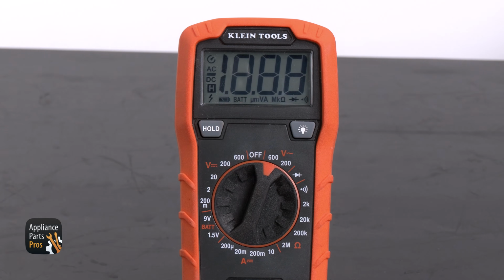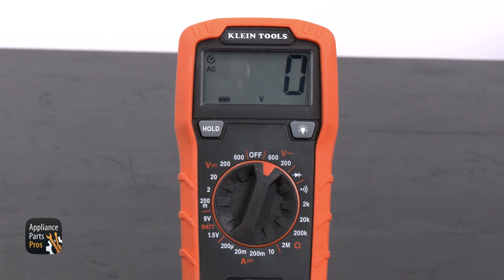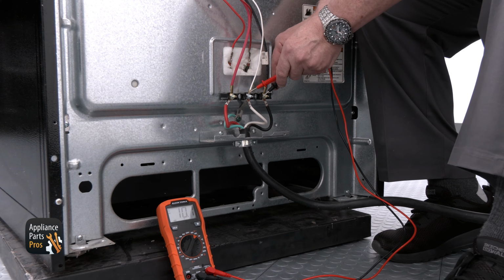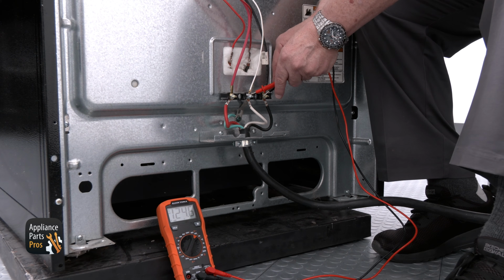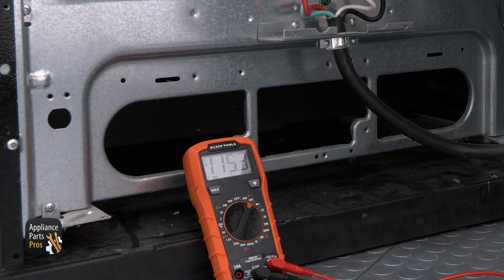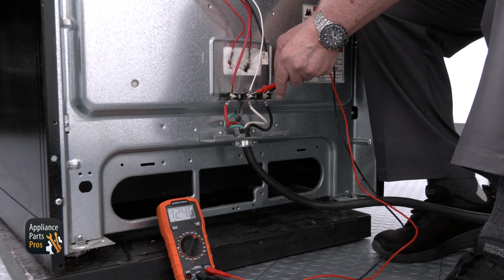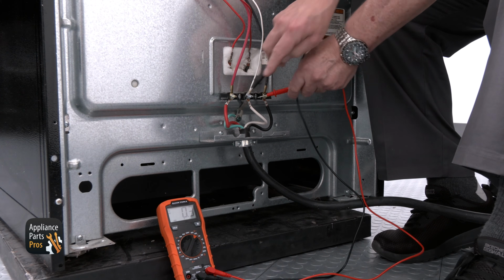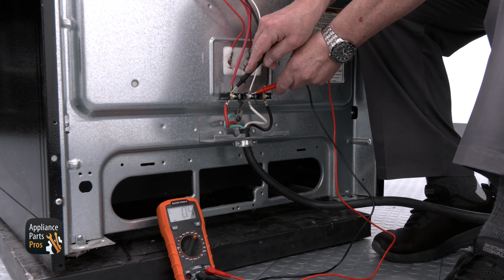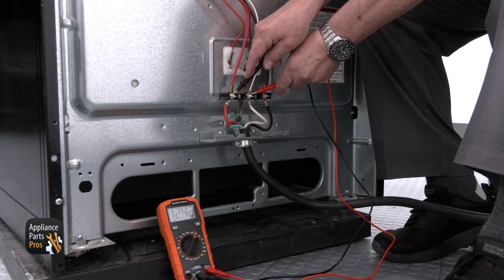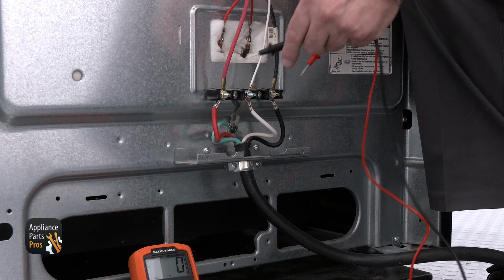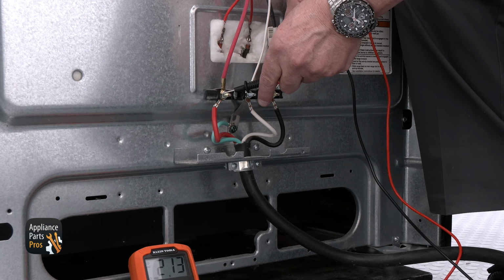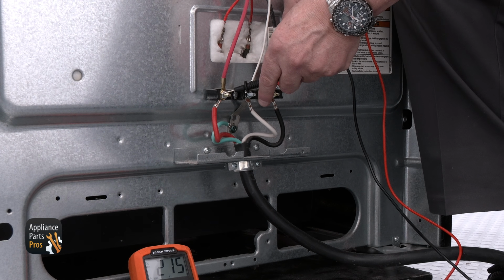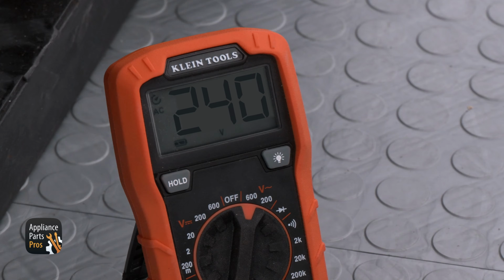Use your multimeter set to volts AC and put one probe on the white terminal and the other probe on the black. You should get a reading of 120 volts AC. Then move the probe to the red terminal and keep the other probe on the white wire. You should see 120 volts AC. Finally, move one probe to the red terminal and the other probe to the black, and you should see 240 volts AC on the meter.